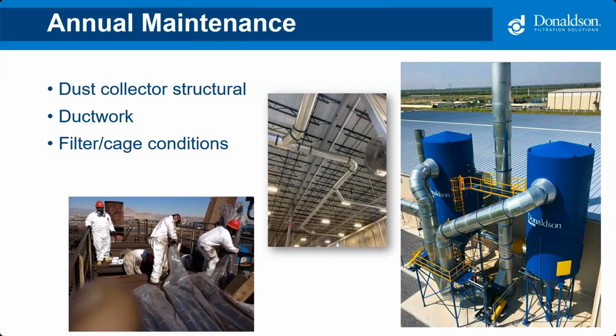You're also going to want to go a little bit deeper looking at your ductwork. Make sure the ductwork is still sealed up properly. There aren't any leaks, because now, right, you're wasting flow rate and you're not going to get the evacuation you need. Also, just make sure that all the hangers that are supporting all that ductwork are still in good condition. Your ductwork's properly supported. As time goes on, again, these inspections become more and more important as your system ages.